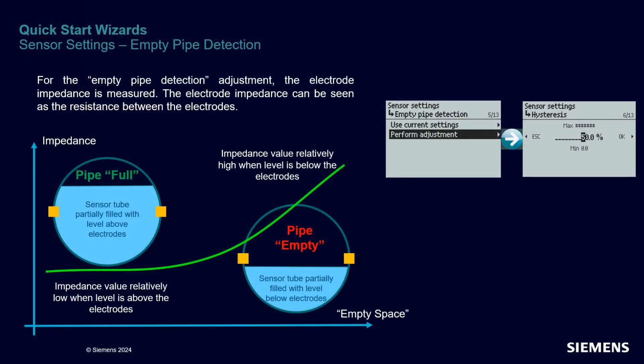The empty pipe detection algorithm is the subject of a short webinar where you can find all the details. At a high level: when a magnetic and conductive medium is present in the pipe between the electrodes, the impedance value measured is relatively low. The opposite is true when the level is low — below the level of the electrodes — the impedance increases. This behavior is what allows the new algorithm to detect what we call the empty pipe detection.